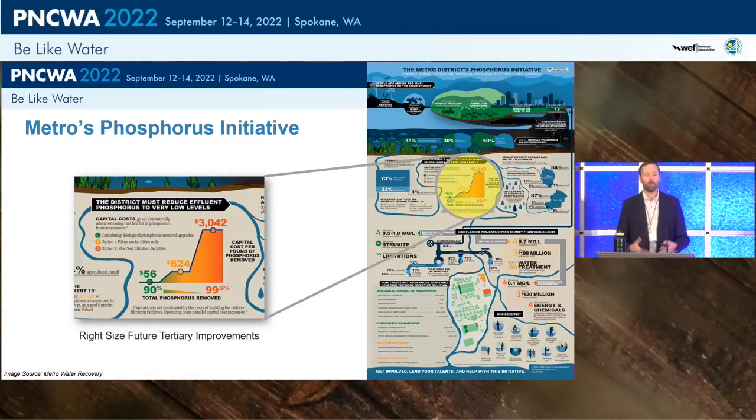Metro Water Recovery developed a comprehensive infographic showing the incremental cost per pound of phosphorus removed — going from about 90-95% removal to 99.9% to reach the 0.1 mg/L future limit. At $3,000 per pound of phosphorus removed, this is a massively expensive project. The utility wanted to right-size future tertiary facilities, so all projects leading up to that future tertiary are designed to minimize those upgrades and costs.